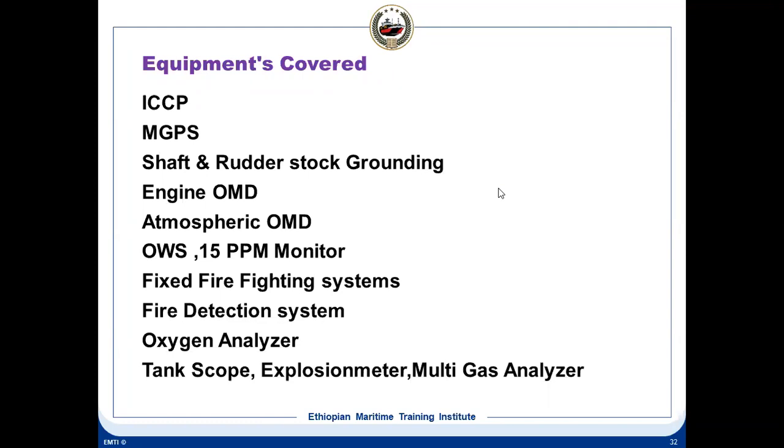Fixed firefighting systems, last class I covered up, except the engine room water mist system, how it is working and under what conditions it works. You need to have one flame and one smoke sensor activated. Then you can test this one, and I showed the sequence in the last class.